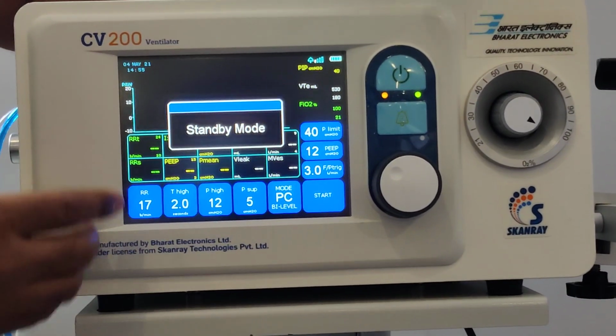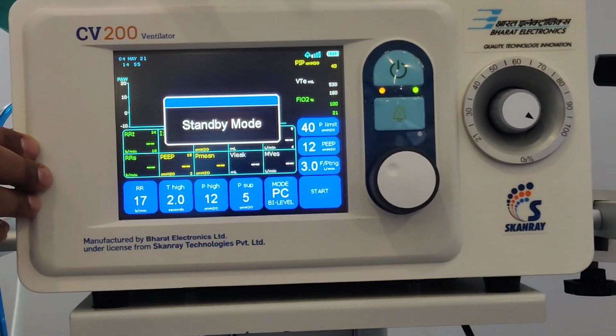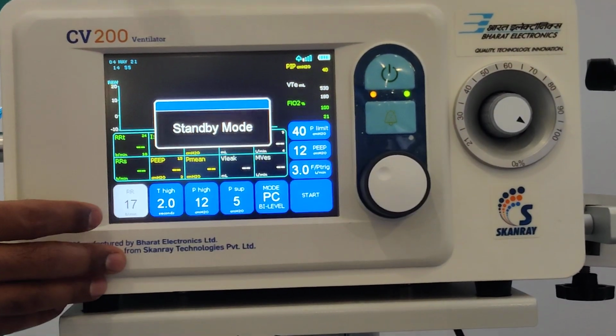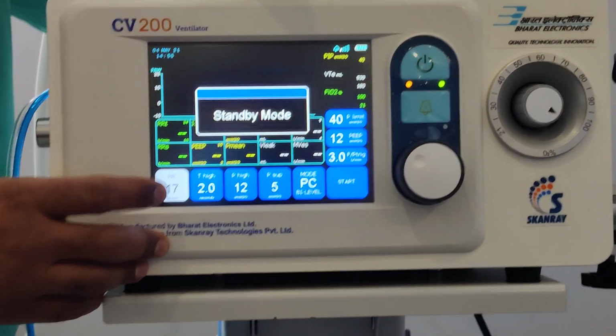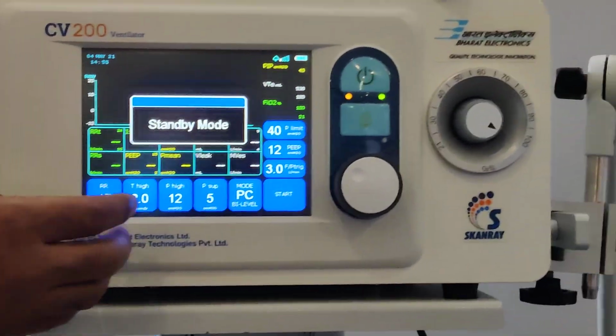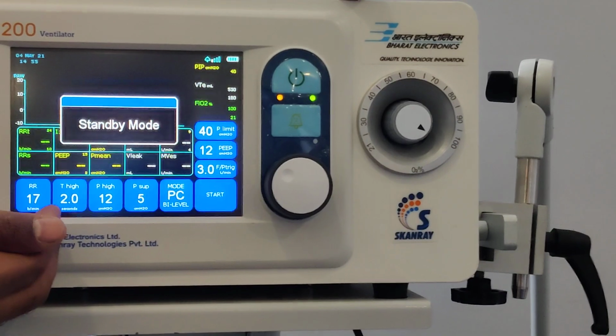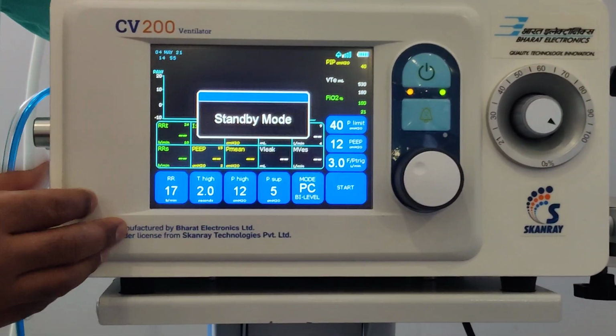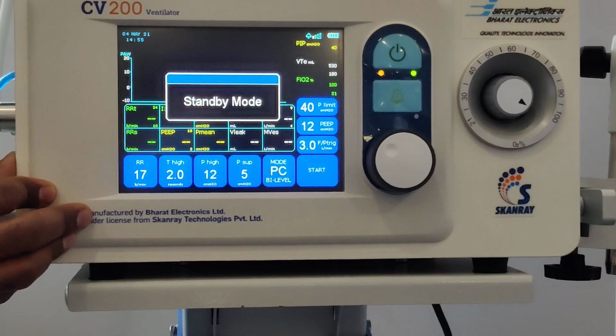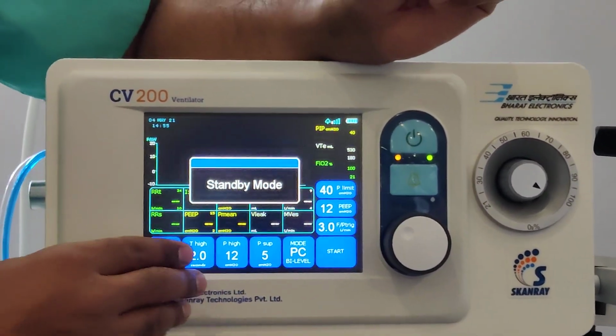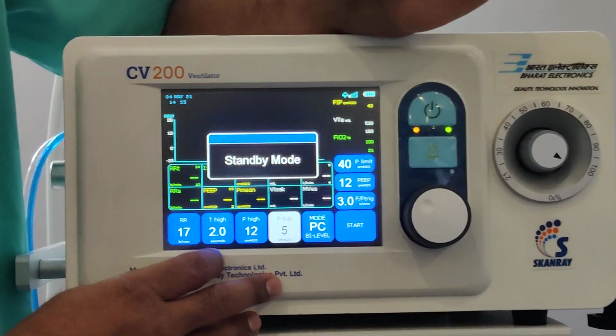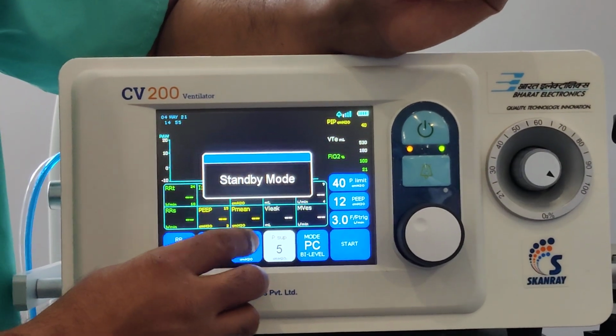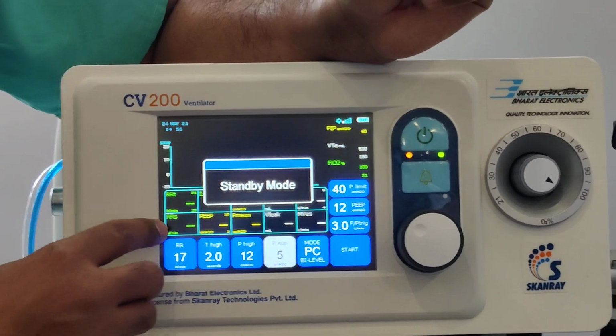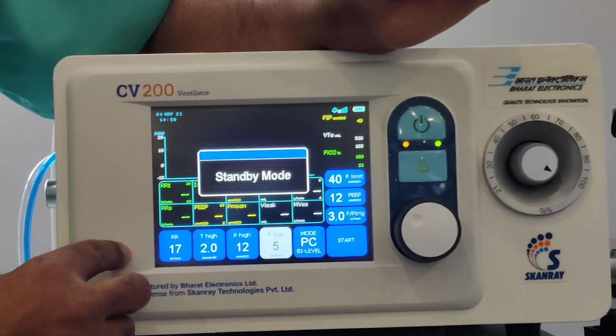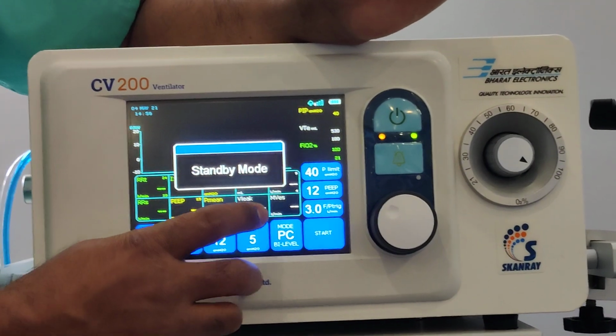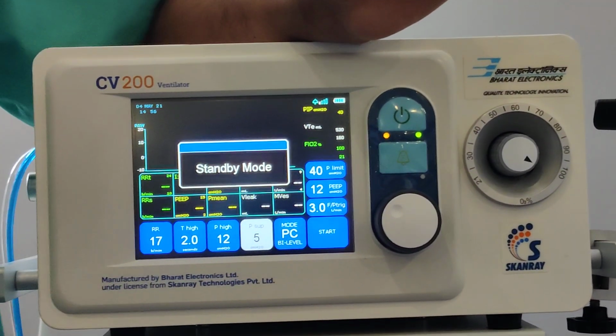Okay, so usually I won't go into too many technical things. Usually we keep this respiratory rate somewhere between 14 to 20. T high is the inspiratory time, the maximum inspiratory time. So you can keep it at 2 seconds. Inspiratory time per respiratory cycle. So you can keep it, it doesn't make a big difference. P high and pressure support. P high is the pressure which the machine gives during this set respiratory rate. And pressure support is the pressure the machine will give when the patient takes a breath on their own.